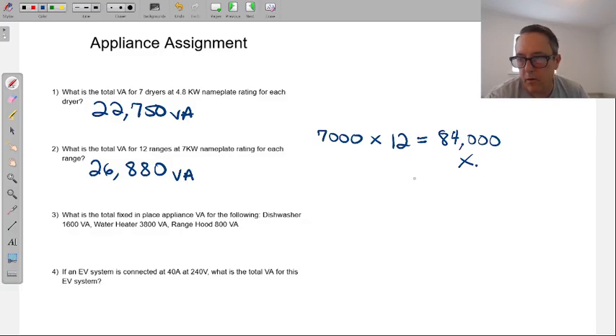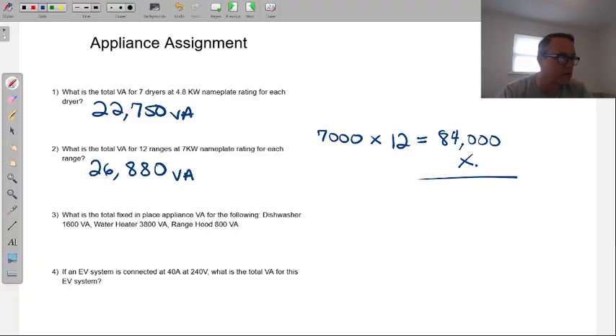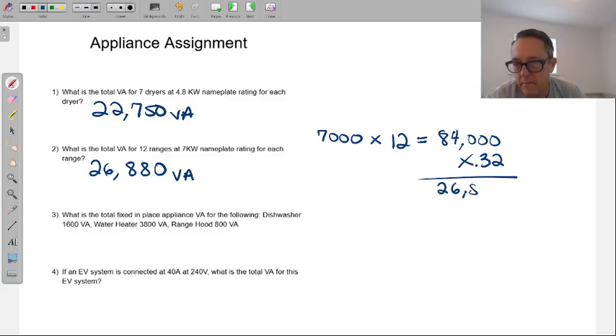The main breaker only has to worry about a percentage of that, which for 12, and here again the right column is everything. Got to make sure you're on column B. There you'll find the times 32 situation. Very good, it checks out that your number is correct. All right, there's our answer to question number 2.